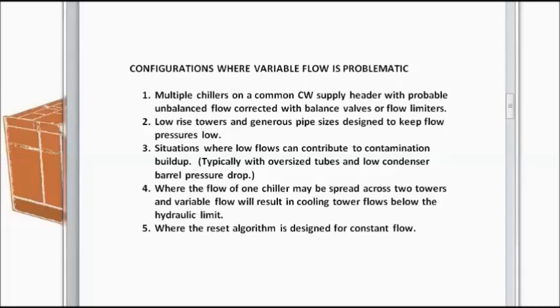And number two is where the typical configurations with cooling towers close to the chillers and generous pipe sizes that ensure low pressure drops. And then there are situations where low flows contribute to significant contamination buildup in the condenser barrels.